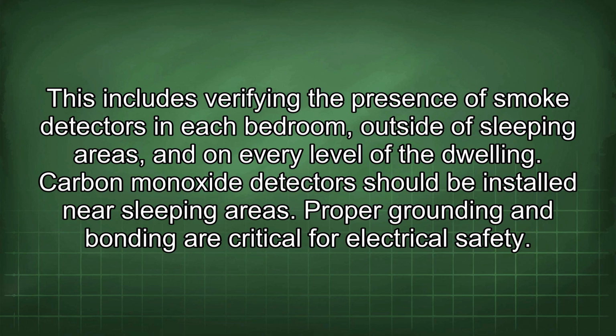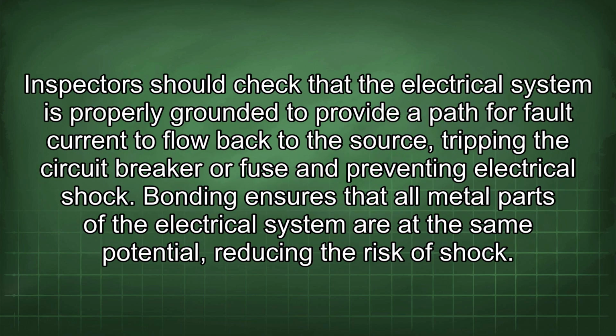Proper grounding and bonding are critical for electrical safety. Inspectors should check that the electrical system is properly grounded to provide a path for fault current to flow back to the source, tripping the circuit breaker or fuse and preventing electrical shock. Bonding ensures that all metal parts of the electrical system are at the same potential, reducing the risk of shock.